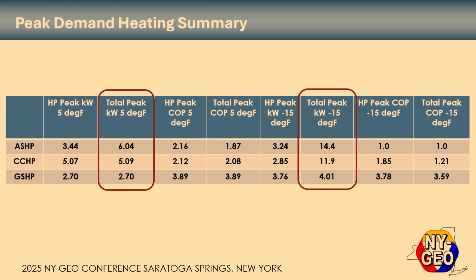And then, of course, we've got heat pump COP and total COP when you take into account electric heat and all that. Essentially, the air source heat pump is running at a COP of 1, and with electric heat, it's a COP of 1, so it's kind of a wash. The cold climate heat pump runs at a 1.85 COP, but when you factor in electric heat at minus 15, it's 1.21. So you can see that our equipment has just a little bit of electric heat that drops the COP down, but we're essentially 3 times the efficiency at those temperatures. So the benefit from a utility perspective is you don't really want to look at 5 degrees if your minimum really is minus 15.